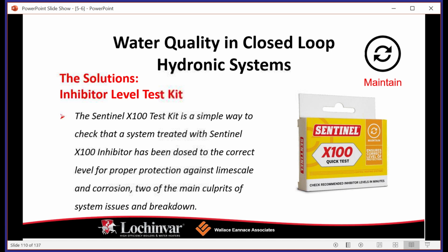But as we all know, it's very rare for us to run into ideal conditions as contractors or mechanics. The X800 can clean the system in an hour. If you have an emergency situation in an old building with cast iron pipes, and you're going to be putting in a condensing boiler, we're going to quickly remove the corrosion. We're going to put in this X800 cleaner, flush it, and we're good to go. The water doesn't need to be hot. You can run it while the boiler is cold. As long as you have flow through the system, you can introduce this to your system, and it's a fast-acting cleaner. On newer systems, we can use the X300.